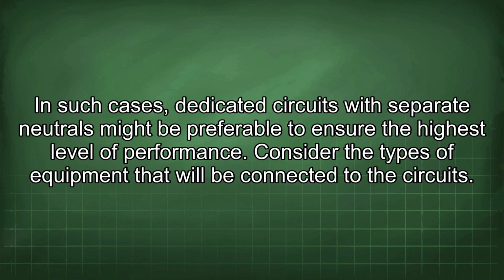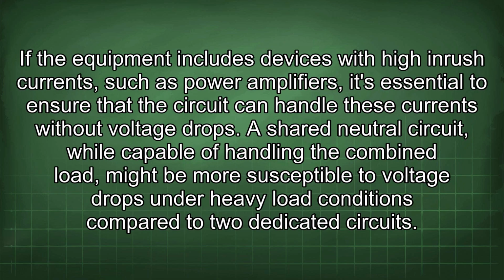Consider the types of equipment that will be connected to the circuits. If the equipment includes devices with high inrush currents, such as power amplifiers, it's essential to ensure that the circuit can handle these currents without voltage drops. A shared neutral circuit, while capable of handling the combined load, might be more susceptible to voltage drops under heavy load conditions compared to two dedicated circuits.